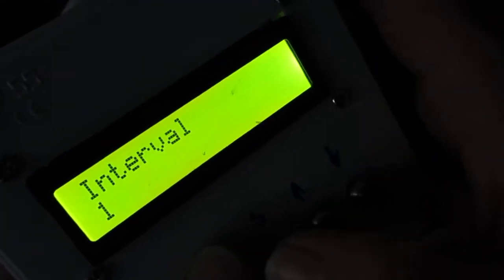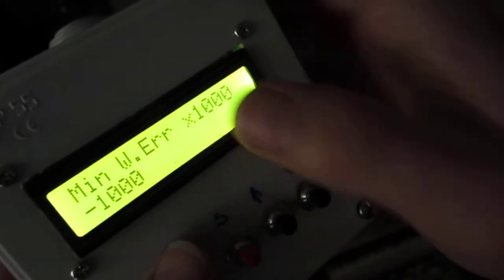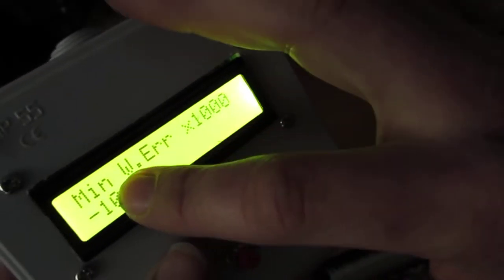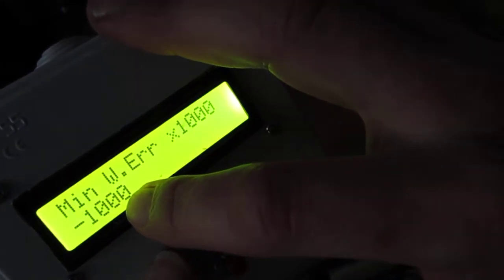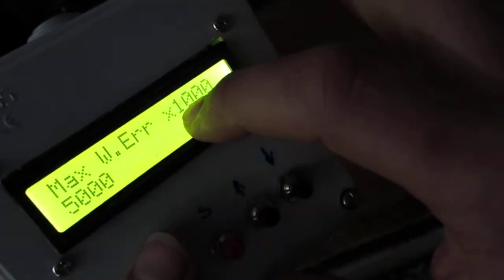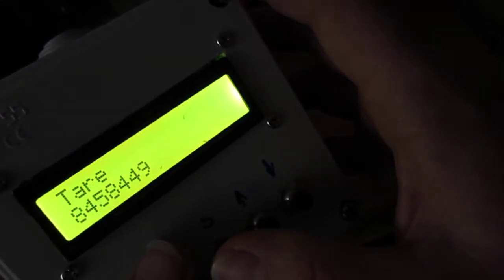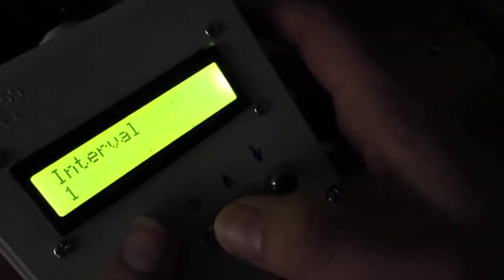We can set the interval of time between weighings, the number of errors that have to be triggered before the final alert is triggered, the minimum weight error threshold, which is now set at 1 kilogram, and the maximum weight error threshold, which is 5 kilograms now. And the tare.